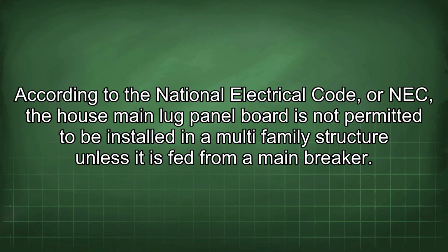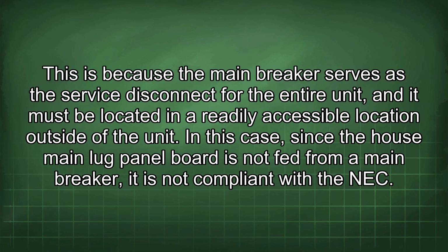According to the National Electrical Code, or NEC, the house main lug panel board is not permitted to be installed in a multi-family structure unless it is fed from a main breaker. This is because the main breaker serves as the service disconnect for the entire unit, and it must be located in a readily accessible location outside of the unit.